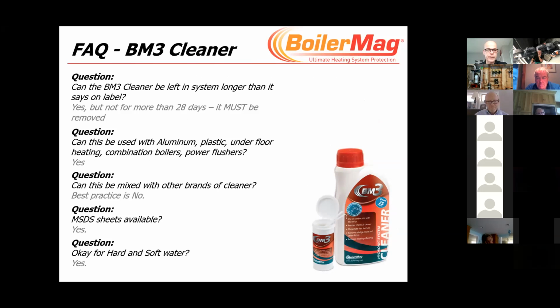The reason for that is we don't want to leave it in there for more than 28 days. It must be removed. If you leave the cleaner in for longer, there's a chance it could start to affect some of the rubber or plastic components in the system, if there is any.